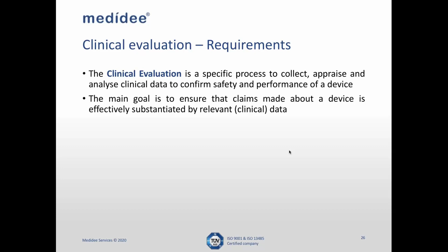You're going to assemble these different data, and you're going to make an appraisal of it, and you're going to identify the information that you can use to justify that your device is first safe and that the device is actually performing as expected. You have to keep in mind that with software, very often we might do performance-based evaluation, where we are able to leverage verification and validation data to demonstrate that the device is performing as expected. But at the end, the goal of this process is to be able to demonstrate that the benefit outweighs the risk. So what you want to demonstrate is that this device has a benefit to be used.